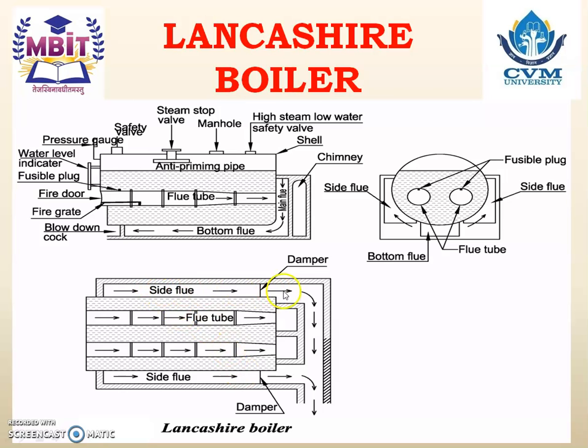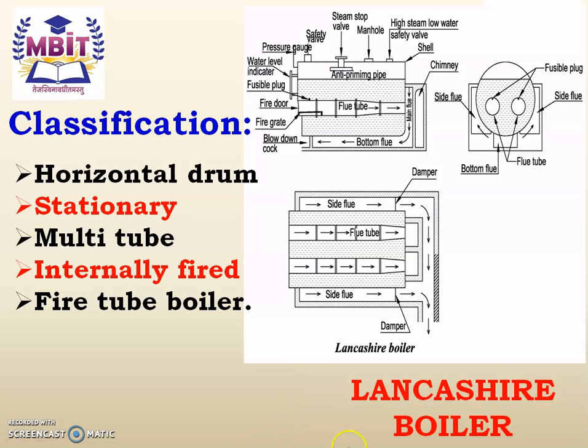From the top view you can see both the tubes, the left hand side passage, and the right hand side passage. Now let us study the classification of the Lancashire boiler. It is a horizontal boiler because the drum is arranged horizontally. It is stationary because the drum is located on a fixed construction and cannot be moved. It is a multi-tube boiler as it has two tubes. It is internally fired, as the fire grate is provided at the front portion of the tube where the fuel is burned inside the boiler drum.